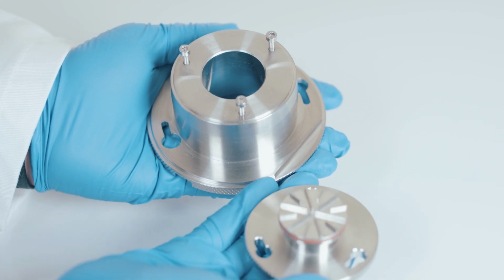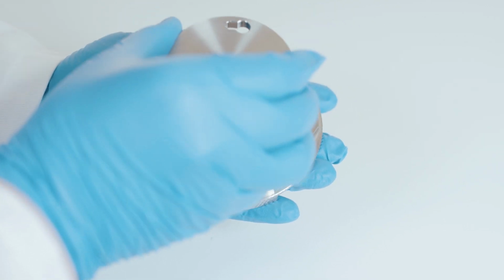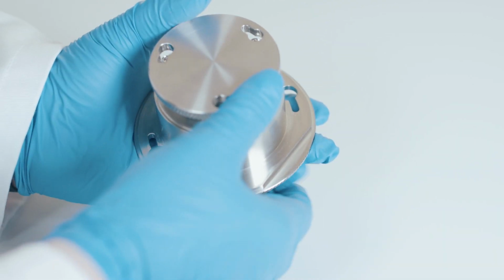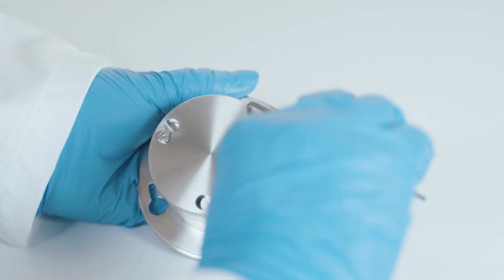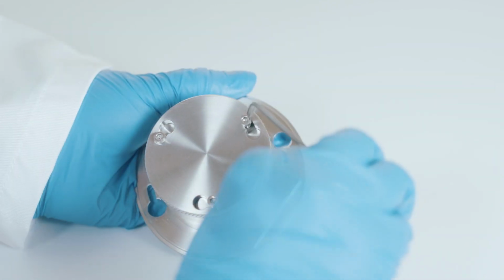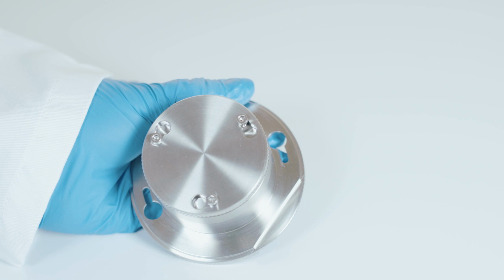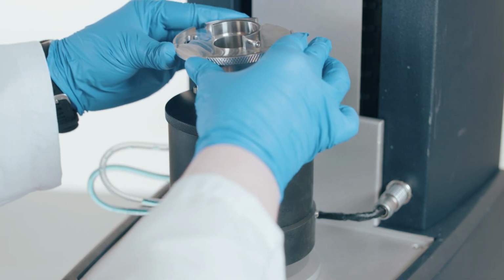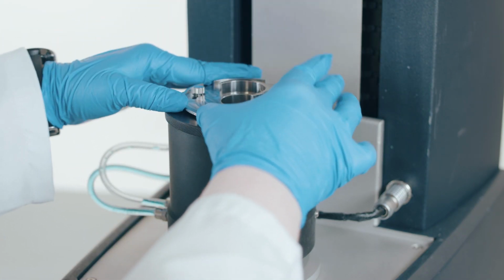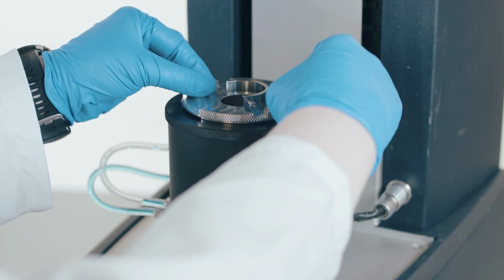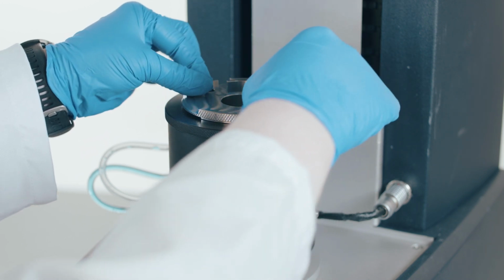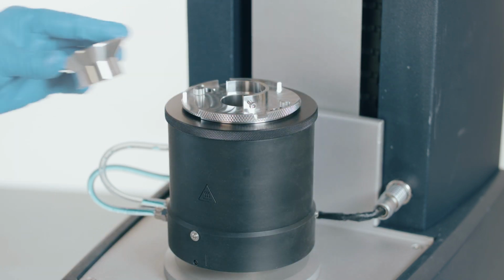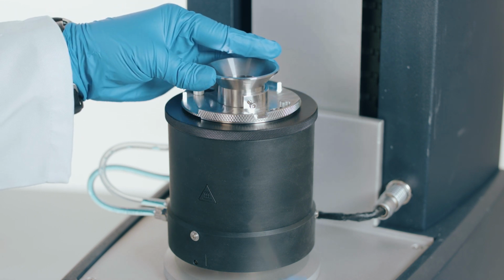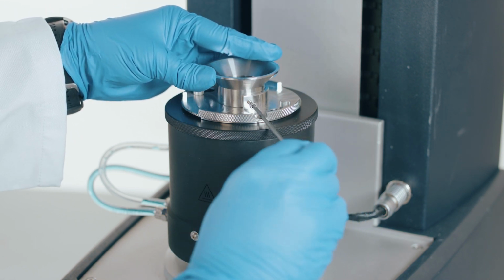The powder shear temperature cell is assembled by placing the shear insert straight down into the cup and securing the screws with the provided wrench. Avoid placing the insert at an angle as this can lead to scratching the cup. The cup is then placed into the Peltier concentric cylinder jacket, rotated into place, and secured with thumb screws. The trim funnel is placed flush with the raised trimming apparatus and secured with the screw.